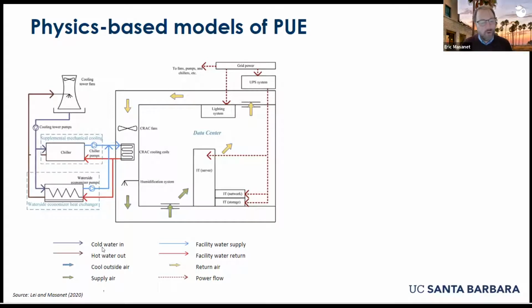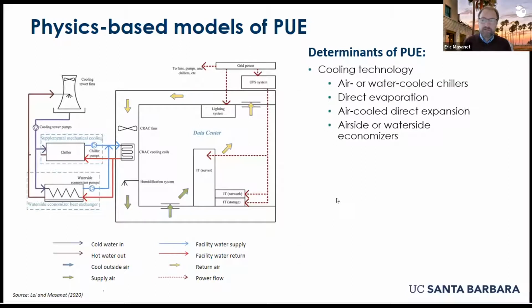That involves water in and water out, cool air from the outside coming in, what are its thermodynamic properties, what's the return air going out, and so forth. Since we can model the physics of the system, we can get pretty good at actually modeling the PUE of data centers, both at the single data center level and up to the average level nationally. And that's because the determinants of PUE are really well captured by models like this.